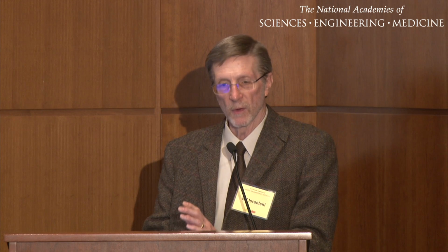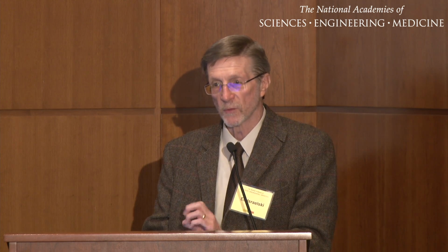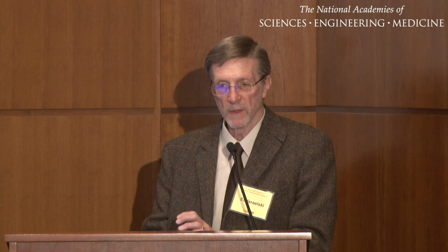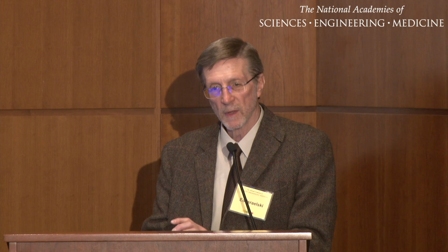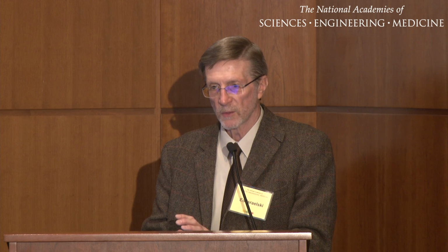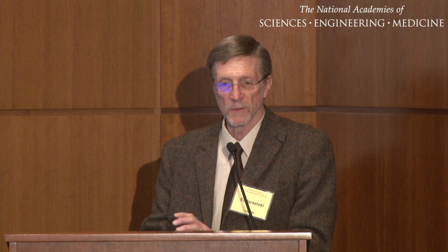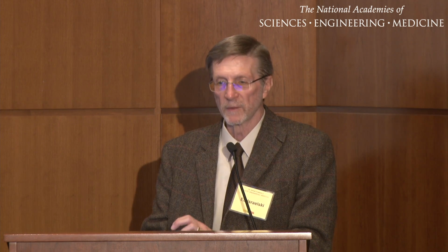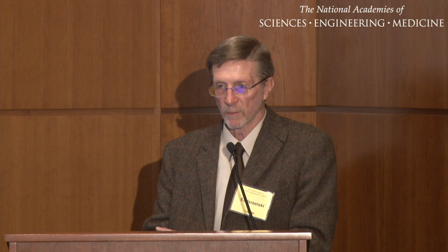So you do this early work called formative because you're forming the design, and then you get to a point where you feel that you can do validation or a summative usability test at the end to show that all this work that you've done cumulative to this point now is going to pay off, and that you'll be able to meet your acceptance criteria and have a product that meets all your user requirements. It's safe, effective, again, applying broadly to a variety of things.